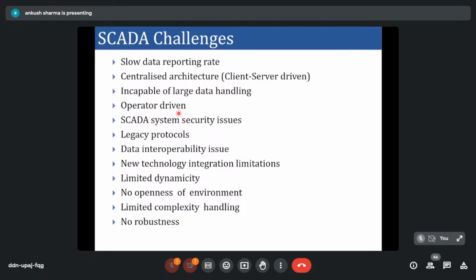Also, the SCADA system is mostly operator-driven, because once an event appears on the single line diagram, the operator has to acknowledge the alarm and take action. So most of the time, an operator has to be present 24/7 to address any event happening in the power system network. That is another limitation of the SCADA system.